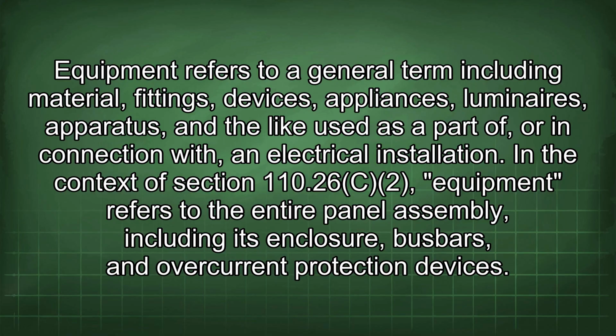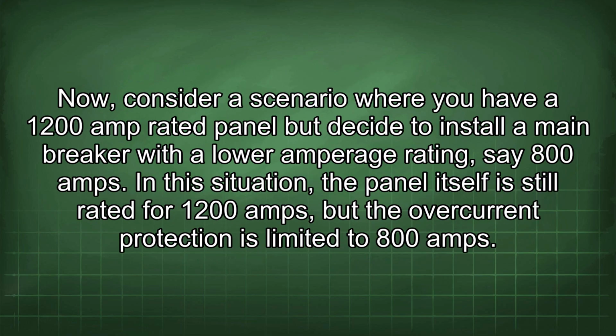In the context of Section 110.26C2, equipment refers to the entire panel assembly, including its enclosure, bus bars, and overcurrent protection devices. Now consider a scenario where you have a 1200 amp rated panel but decide to install a main breaker with a low amperage rating, say 800 amps.